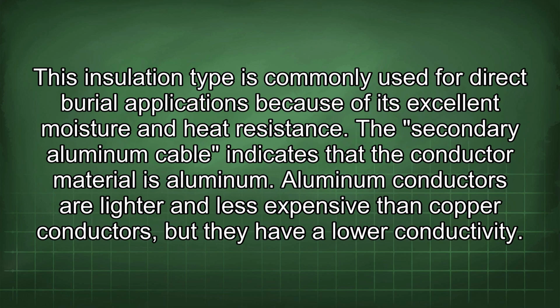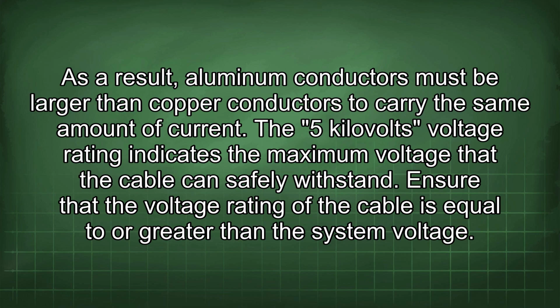This insulation type is commonly used for direct burial applications because of its excellent moisture and heat resistance. The secondary aluminum cable indicates that the conductor material is aluminum. Aluminum conductors are lighter and less expensive than copper conductors, but they have a lower conductivity. As a result, aluminum conductors must be larger than copper conductors to carry the same amount of current. The 5 kV voltage rating indicates the maximum voltage that the cable can safely withstand. Ensure that the voltage rating of the cable is equal to or greater than the system voltage.